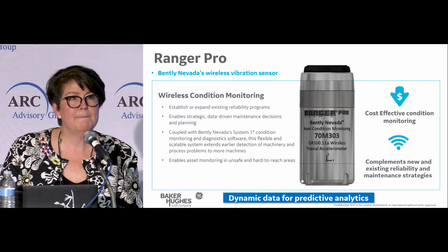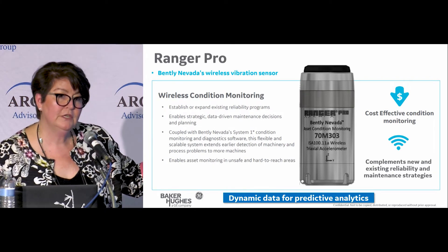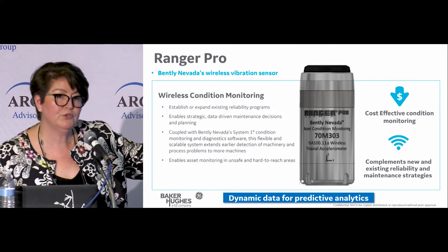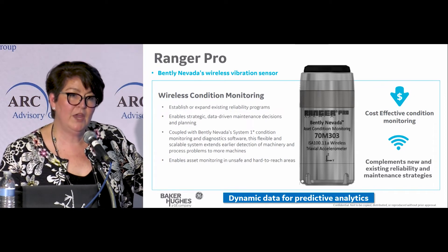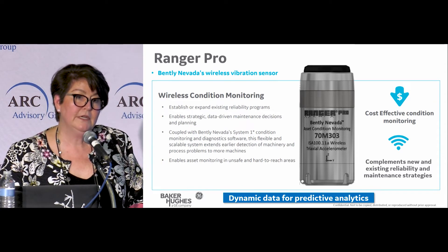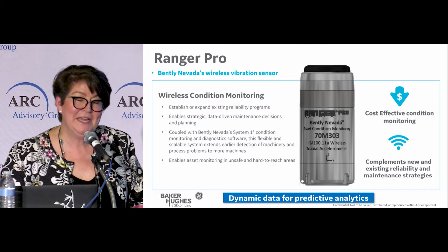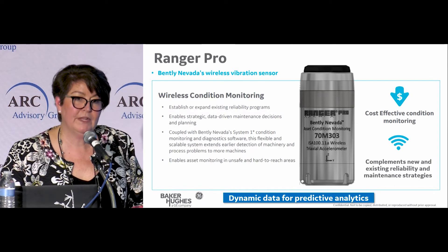I believe the temperature range is about minus 40 to about 150 degrees Fahrenheit. This is a very modular accelerometer and we have other planned enhancements and releases. The electronics and crystals in the bottom section — we're talking about separating that, putting it on the machine, then having a cable run to the power supply and the e-module, which is the wireless capability on top. Today the device is ISA100. A little later in 2019 we'll also have WirelessHART, and we have some customers interested in LoRa, though the challenge is the amount of dynamic data and LoRa's capabilities. The key is we're not developing on a proprietary protocol — we're developing on current standards today.